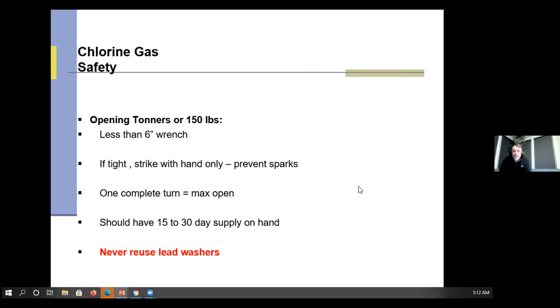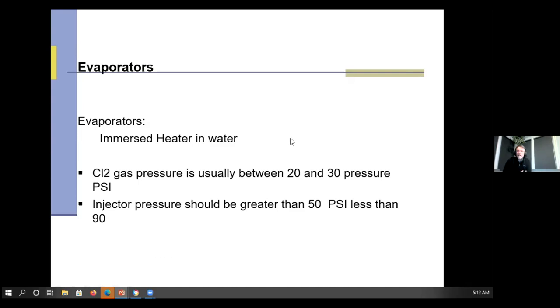It's super important to have a 15 to 30 day supply of chlorine. In some older and not widely used gas systems, they use something called an evaporator — they put the chlorine cylinder in an immersed heated water bath, almost like a hot tub, and that creates the pressure to deliver the gas into the system. Some gas pressures are usually between 20 and 30 PSI and injector pressure should be greater than 50. These are not testable — each system will be a little bit different.